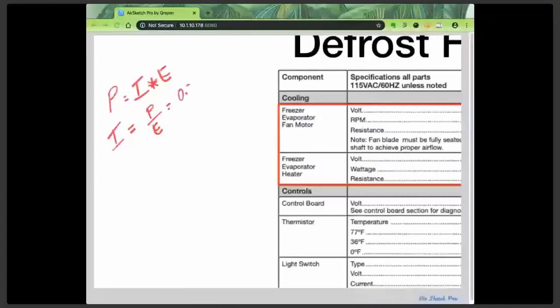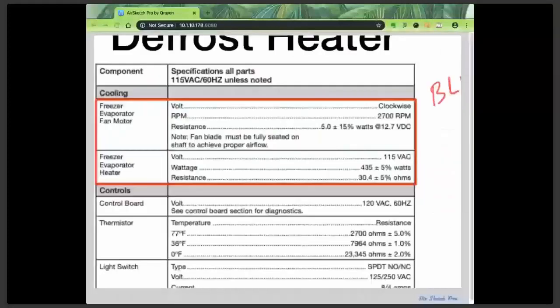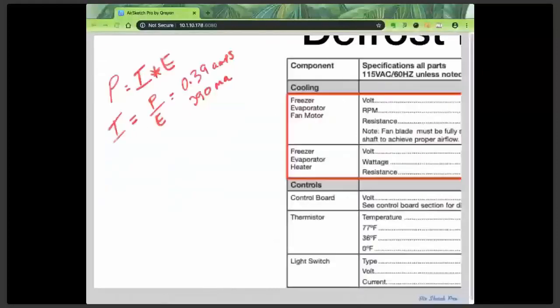That's supposed to be a 3—0.39 amps, or 390 milliamps. And if I apply the tolerance they've given me, plus or minus 15%, then I know that if I read anywhere from 330 milliamps to 450 milliamps, I'm in spec within the tolerance given.